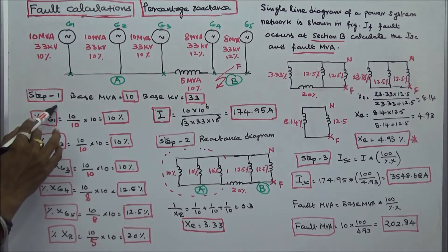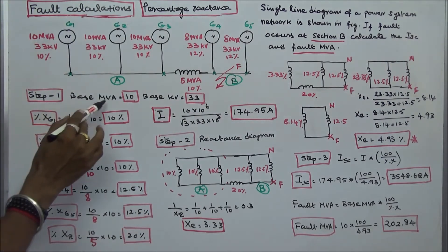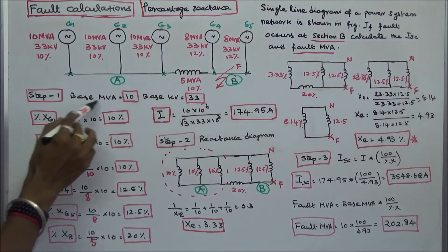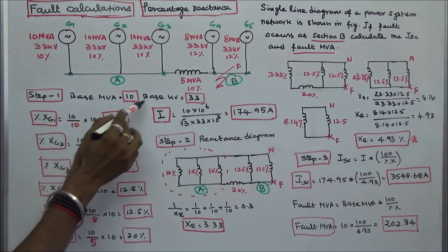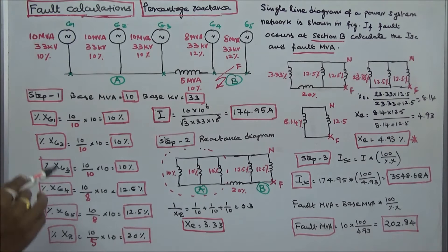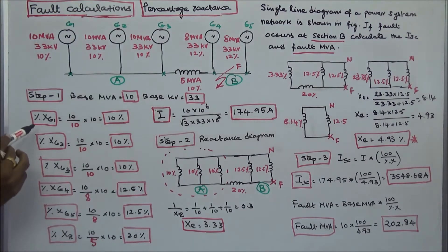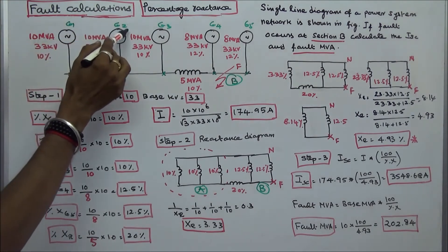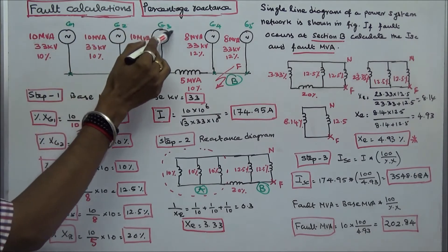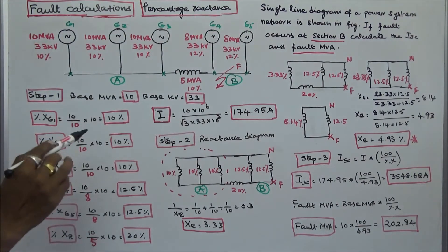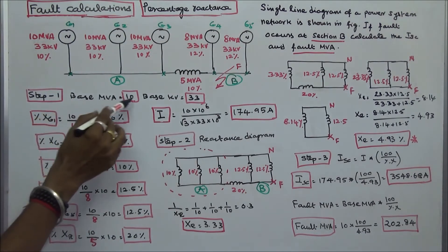Step 1: Choose base MVA and base kV. Base MVA is equal to 10, and base kV is equal to 33. Next, I have to calculate the percentage reactances of XG1, XG2, XG3, XG4, and XG5 based on this base MVA.